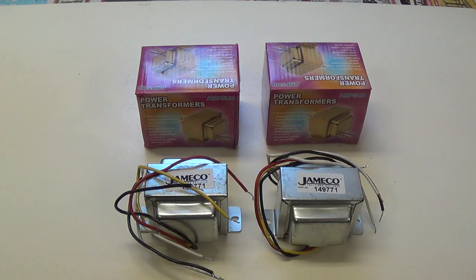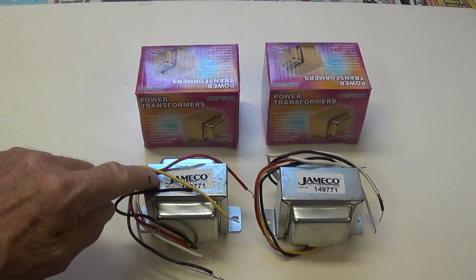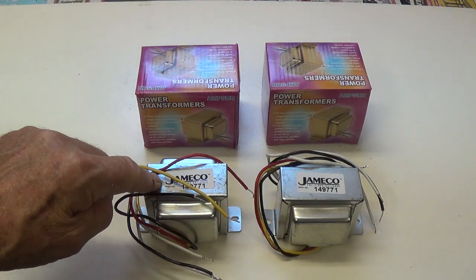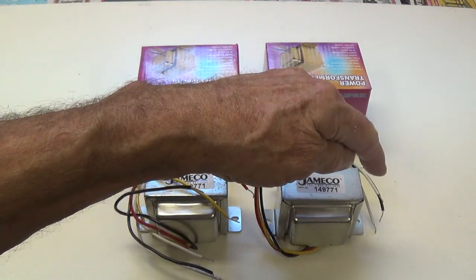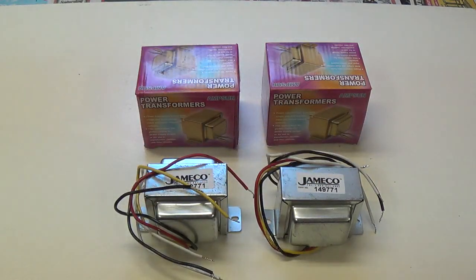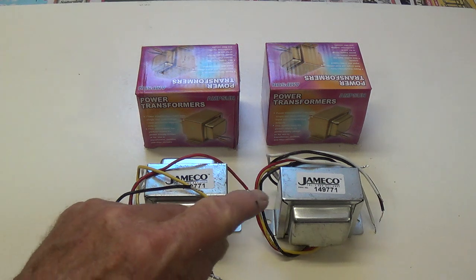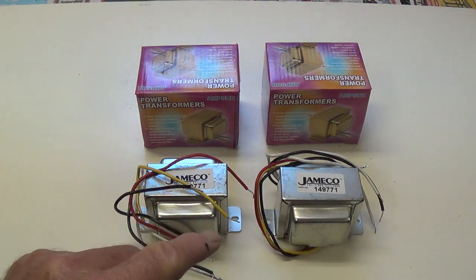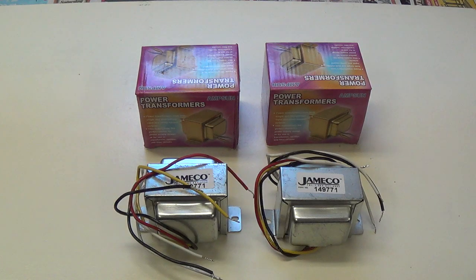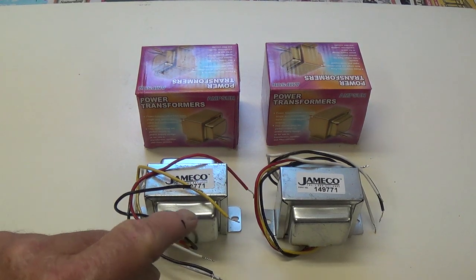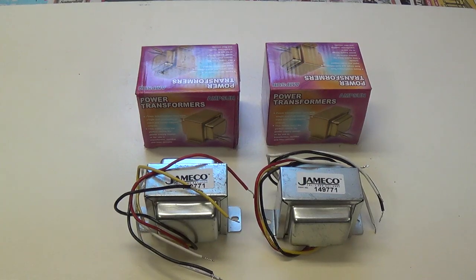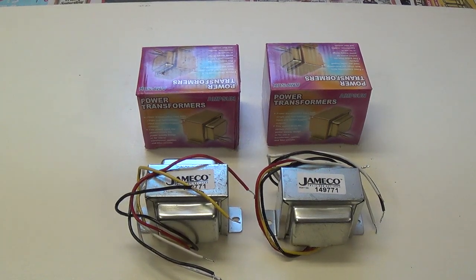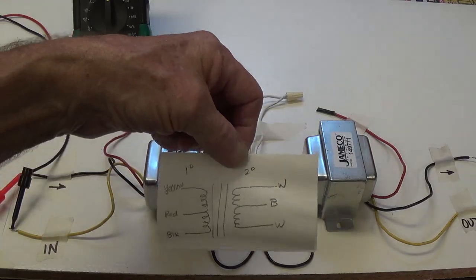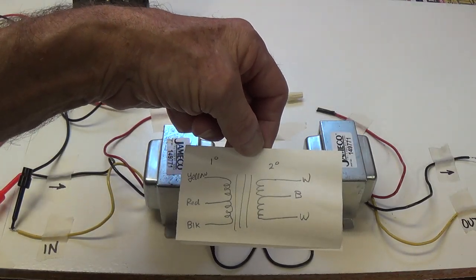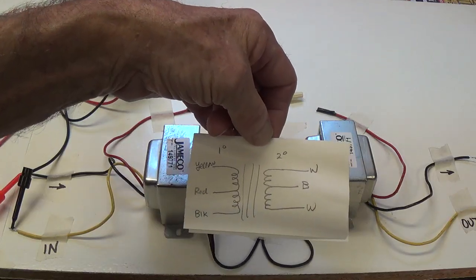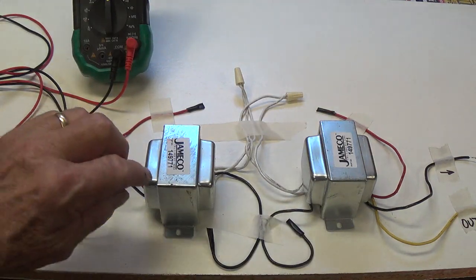Now, since receptacle voltages have gone up in the United States to around 120 volts, some slight reduction down to like 110 or 115 might actually be beneficial. But if it drops way down like around 90 or so, I don't think it's going to be usable. So there's only one way to really find out, and that is let's assemble these together and make our own isolation transformer.